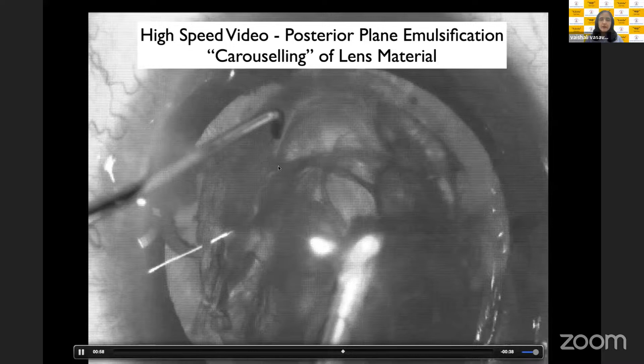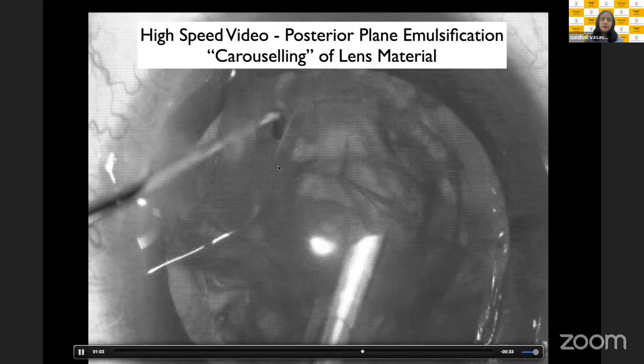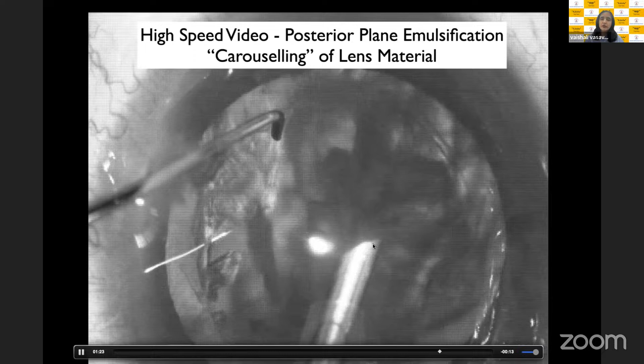So even with a lower vacuum, if you have a good technique where you don't occlude your tip all the time as much as possible, your flow rate helps your ultrasound and your vacuum to remove this material. You will see that the chopper is not moving, the phaco tip is not moving, and yet things are happening. It's swirling in, as it were. This is what a technique will do, and this is how you can reduce surge. Even in this slow motion, you see that there are no micro fluctuations in the anterior chamber because the phaco tip is very rarely completely occluded. If you keep hearing a ting, ting, ting sound on your phaco, that means you need to use your chopper to push that material away and reposition it so that there is no complete occlusion. I think this is the point I wanted to bring about.